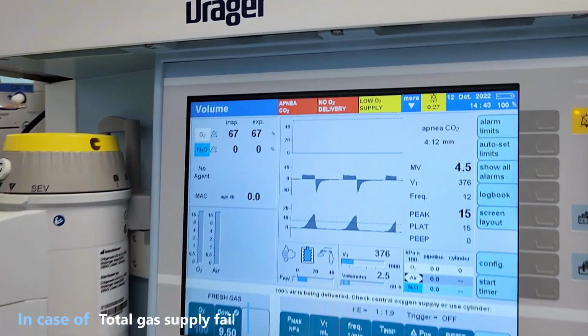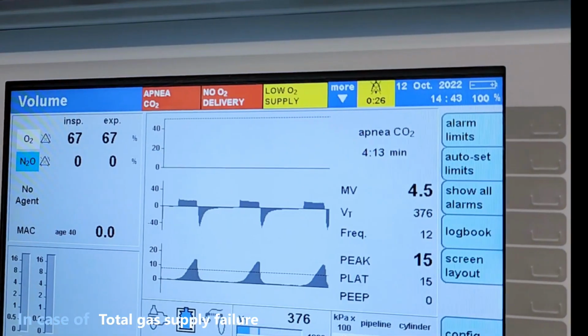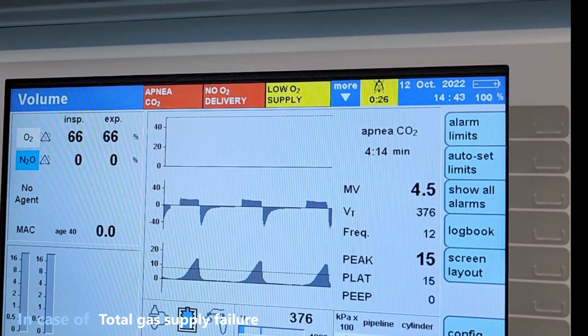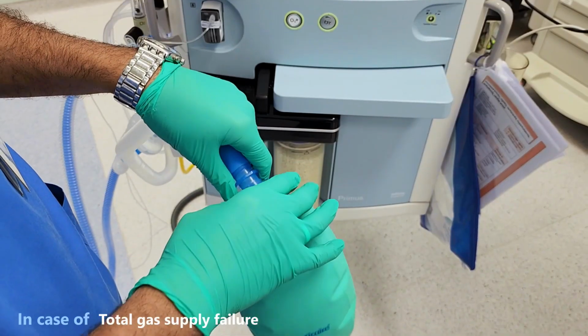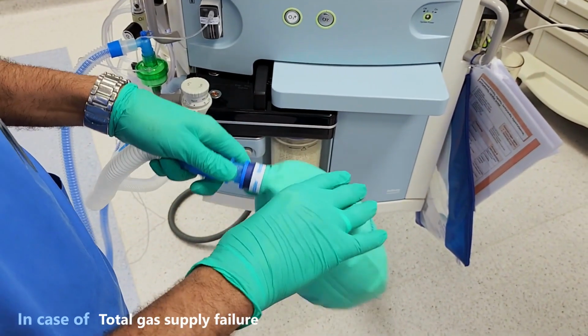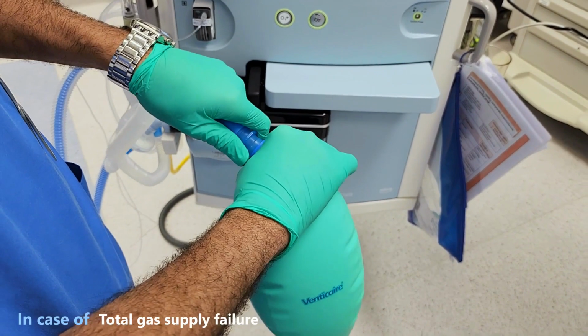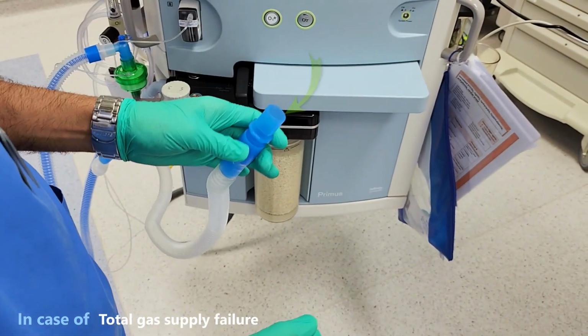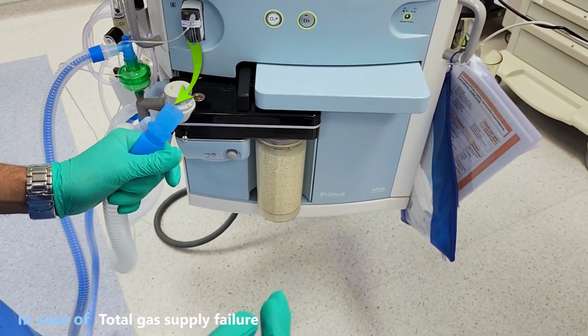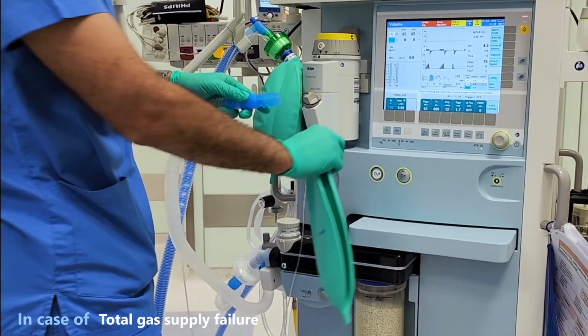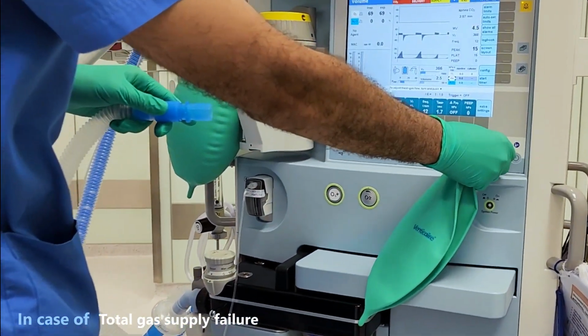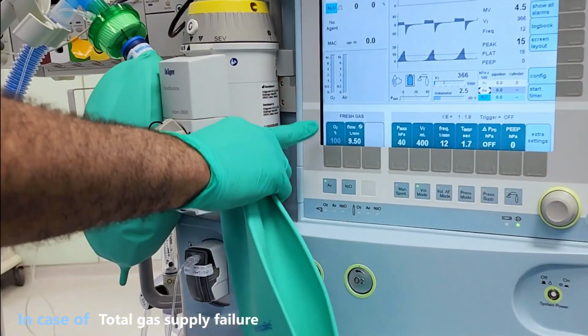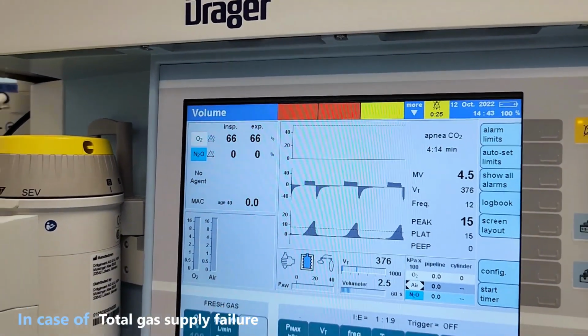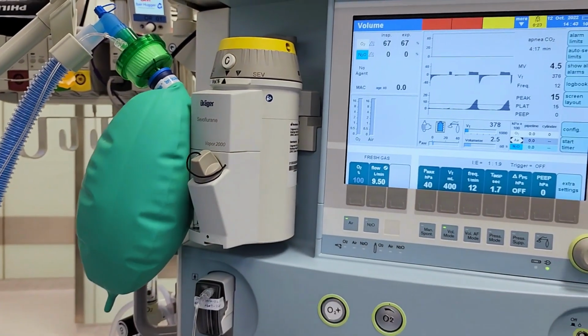In case of total gas failure, with no pipeline supply and the oxygen cylinder empty, we can still use the machine to ventilate the patient. What we have to do is just remove the reservoir bag. The machine will start to suck in ambient air and ventilate the patient with 21% oxygen. You will be able to adjust the flow and ventilator parameters. As you can see here, there is no gas supply at all, but the ventilator is still working.